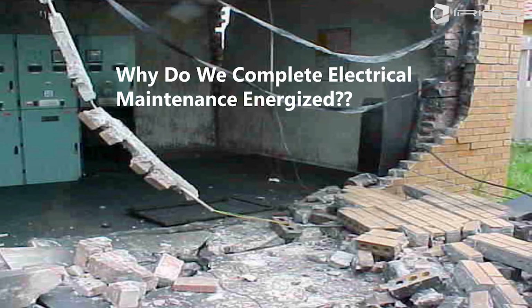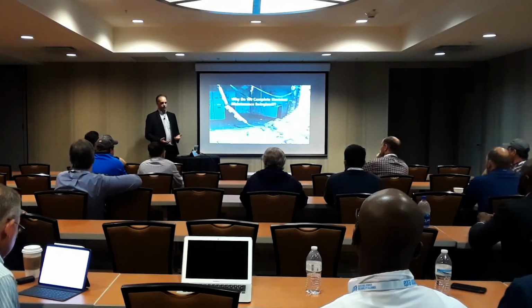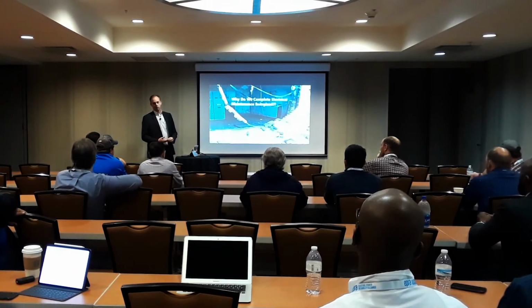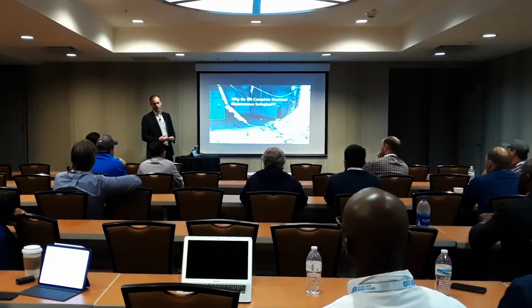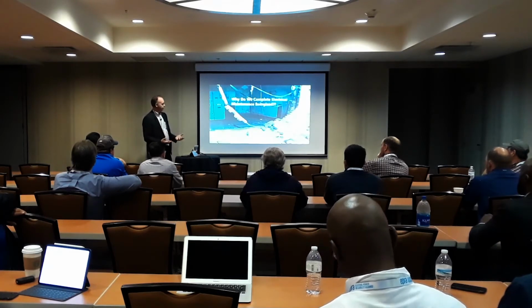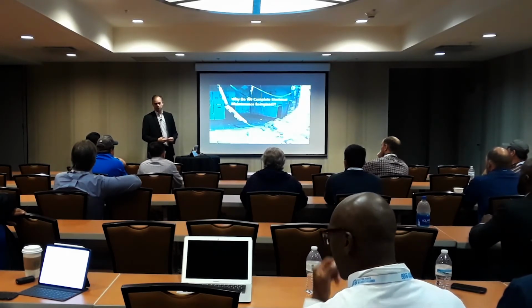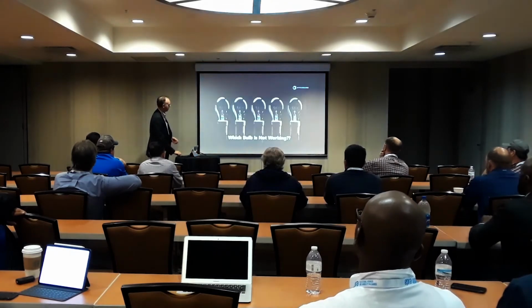We take it for granted that the lights are on, that the electric heat is running, that the motors are running, and then when it goes away, all hell breaks loose. And when these things fail, they can fail catastrophically as well. There's a lot of available fault energy there, and when something does fail, if we have an insulation breakdown and an arc to ground or a phase-to-phase fault, significant amounts of energy can be released, and there can be catastrophic consequences for the facility as well.